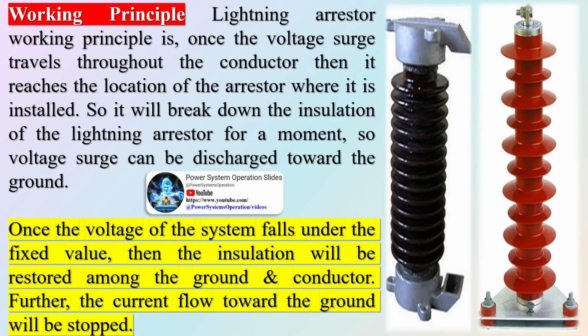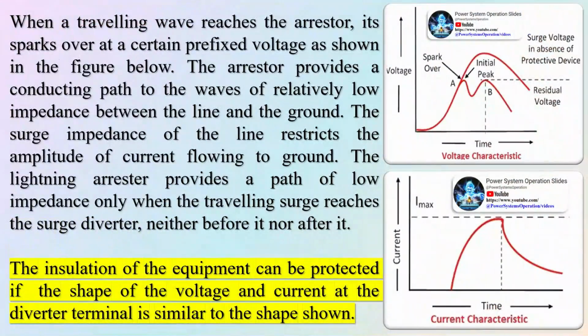The following are the damages that are caused by the traveling wave on the substation equipment. The high peak or crest voltage of the surge may cause flashover in the internal winding, thereby spoiling the winding insulation. The steep wave fronts of the surges may cause external flashover between the terminals of the transformer. The highest peak voltage of the surge may cause external flashover between the terminals of the electrical equipment, which may result in damage to the insulator.